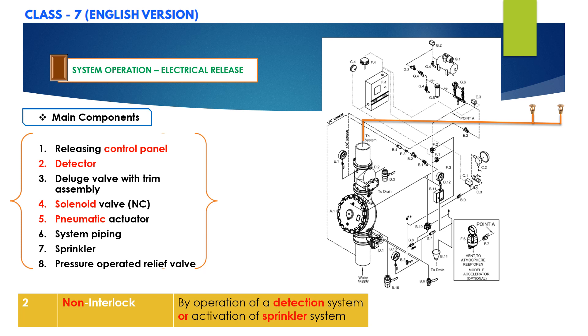When the deluge valve operates, the sensing end of the pressure-operated relief valve (PORV) is pressurized, causing the PORV to operate. The PORV continually vents the priming chamber to prevent the deluge valve from resetting, even if the open releasing devices close. The deluge valve can only be reset after the system has been taken out of service and the outlet chamber and associated trim piping are depressurized and drained.